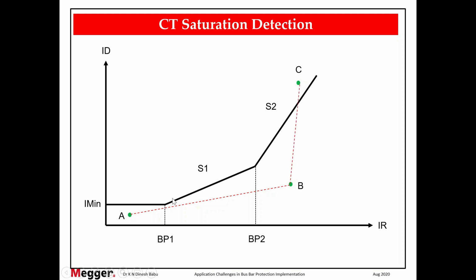Now what happens? A to B, B to C. Even if the point is above the curve, the relay will not issue trip because it knows the locus. ABC means external fault CT saturation. Now you just see, if this slope 2 is configured like 79% or even 80% or 90%, nothing will happen, because the relay is following locus theorem. That's what I was telling. Even if your settings are not 100% accurate, the relay will work perfectly as per the requirement.